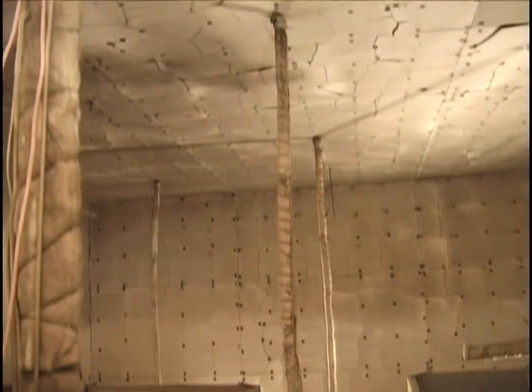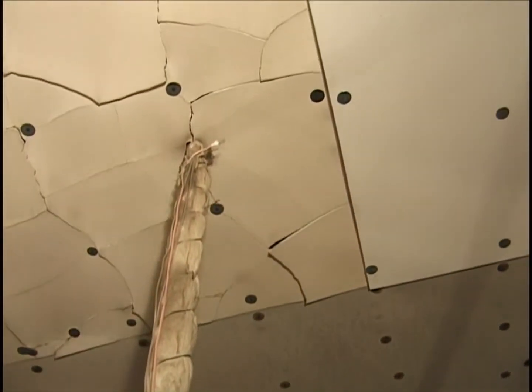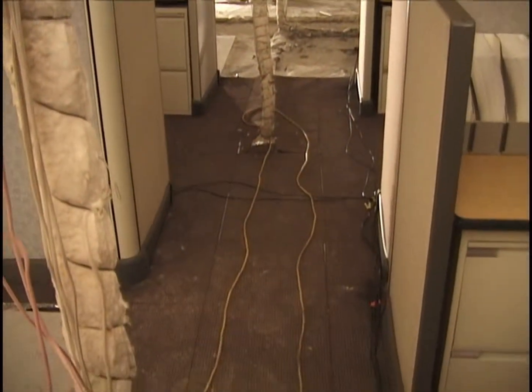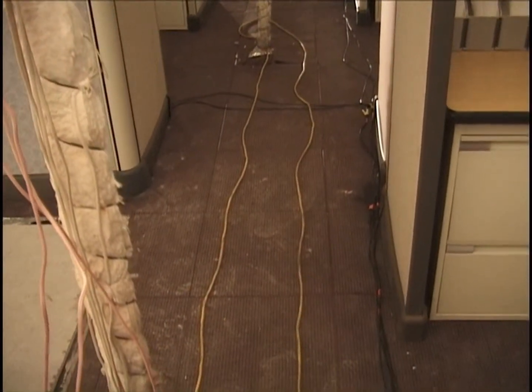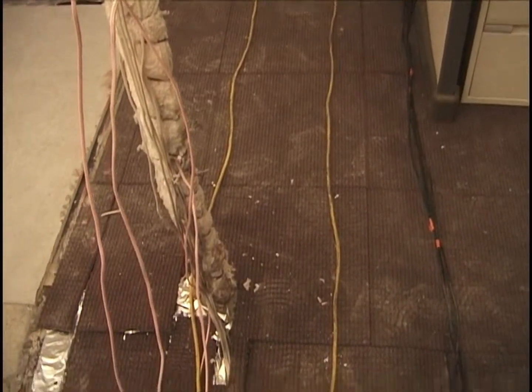Number 2, and there's the one all the way to the top, which is the cracks in the ceiling tiles. And this will be a Jet A ignited fire. So there'll be the usual 4 liters per cubicle plus an extra liter on the carpet here.